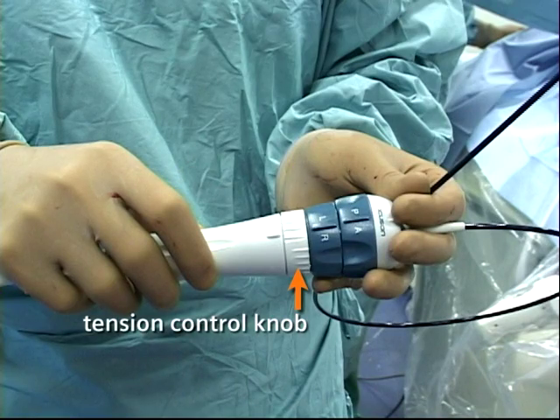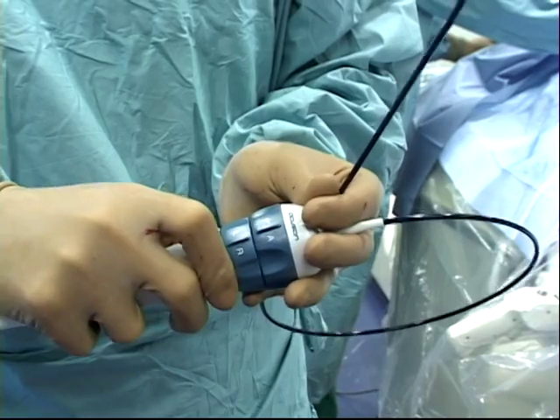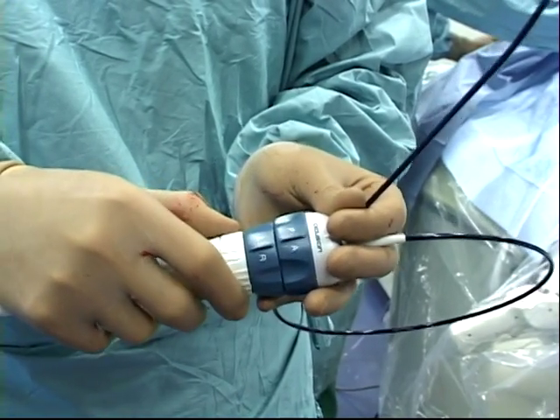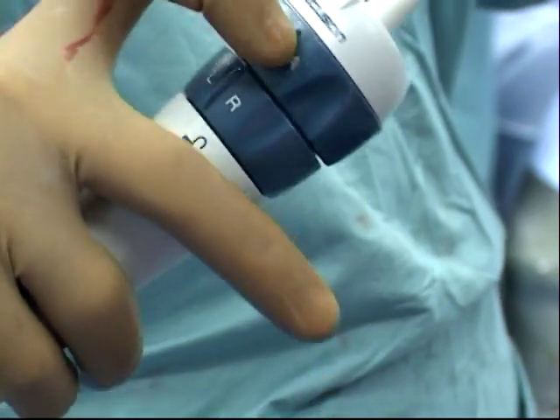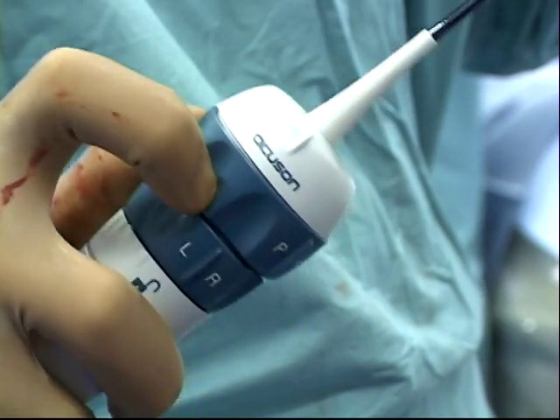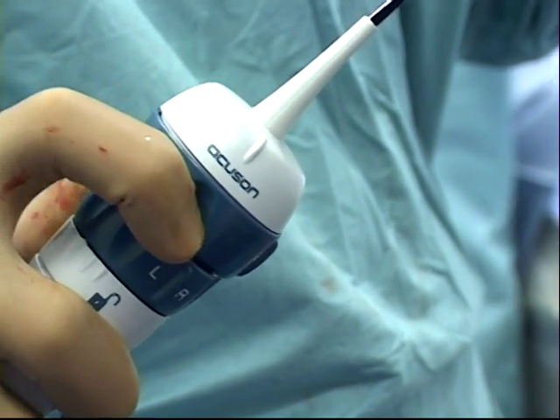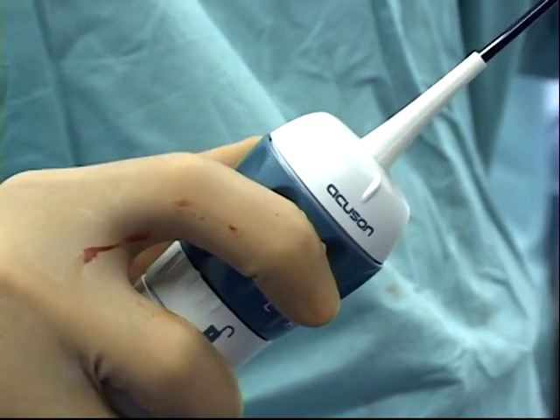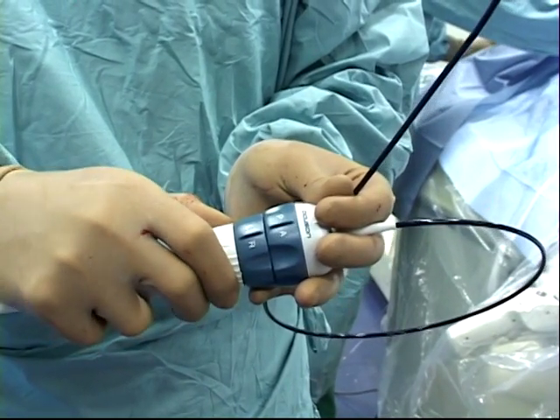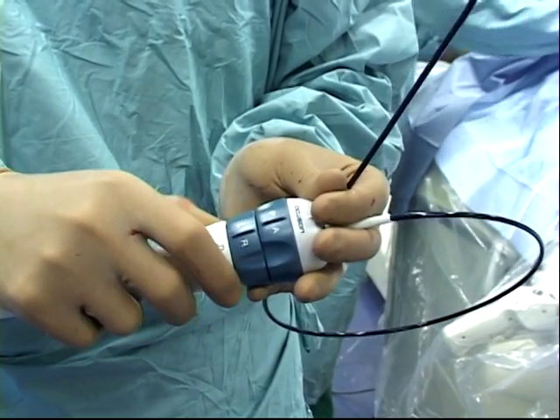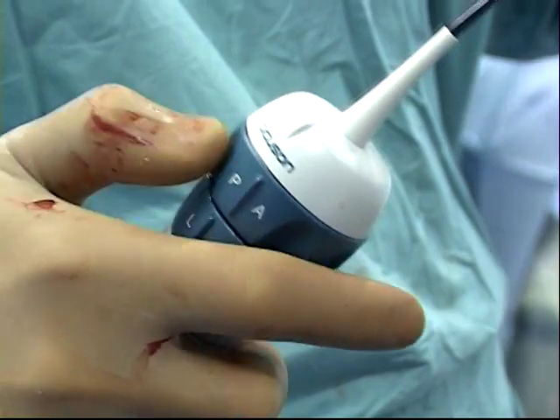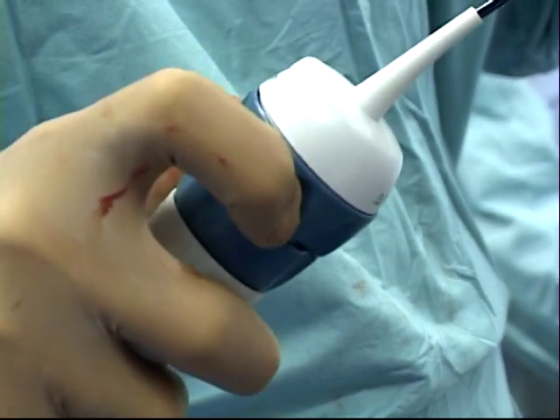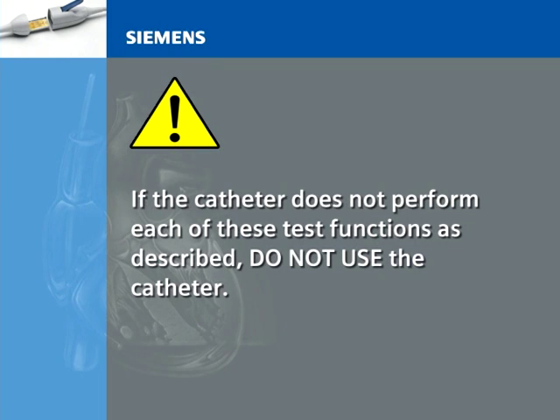To evaluate the tension control knob, increase the resistance by turning the knob clockwise, then steer the catheter in any direction. An increase in resistance of the catheter steering should now be noted when using the steering knobs. To decrease the resistance, turn it counterclockwise, and then steer the catheter in any direction. A decrease in resistance of the catheter steering should now be noted. If the catheter does not perform each of these test functions as described, do not use the catheter.